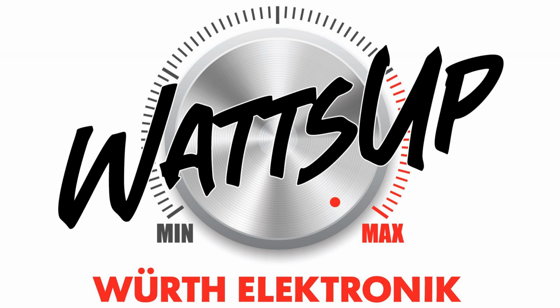Now, if you look at electronic current transformer modules, or electronic current sensor modules is a better way to word it, they come in many types, such as Hall effect sensors, flux gate sensors, and even fiber optic current sensors. These modules offer advantages for certain applications, such as weak field detection and measuring DC current. The downsides can be high cost of the module, size, and accuracy, all depending on the type that's chosen.